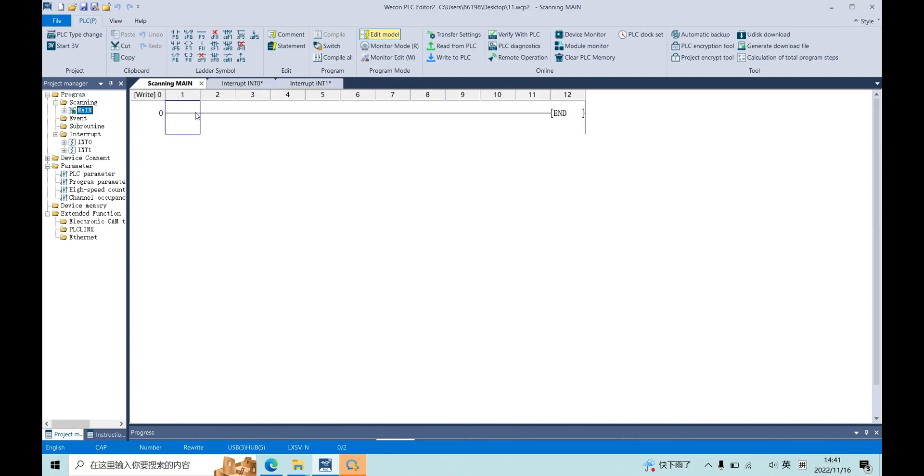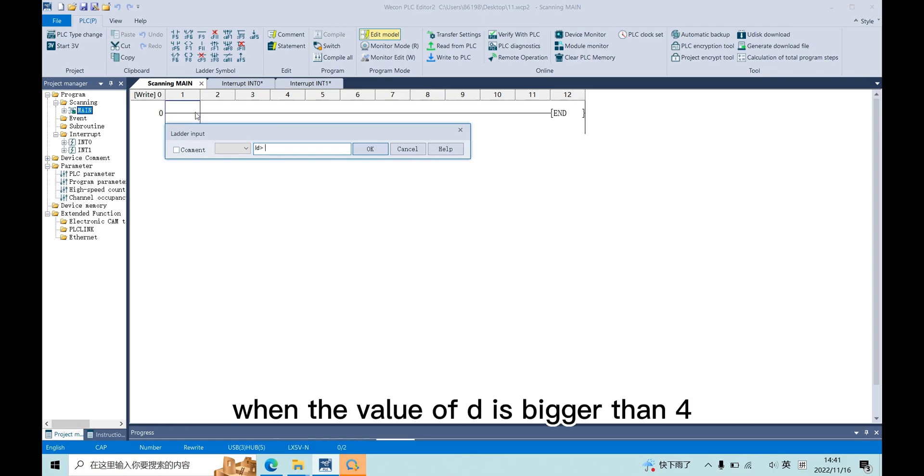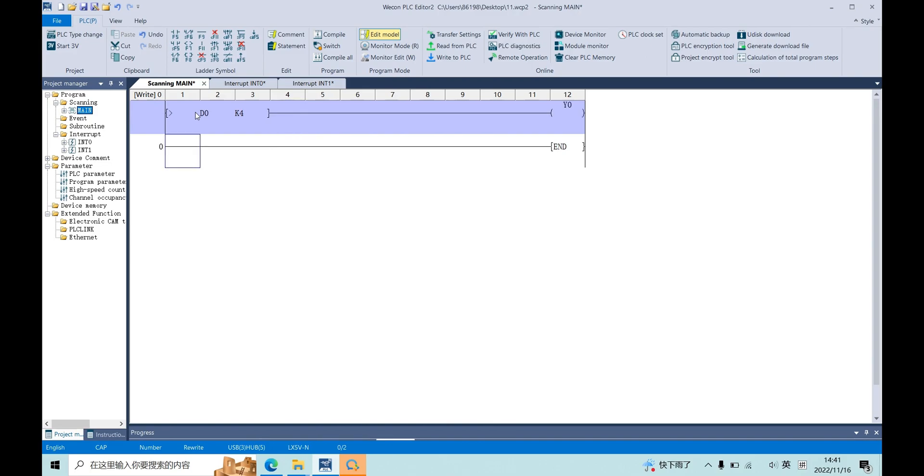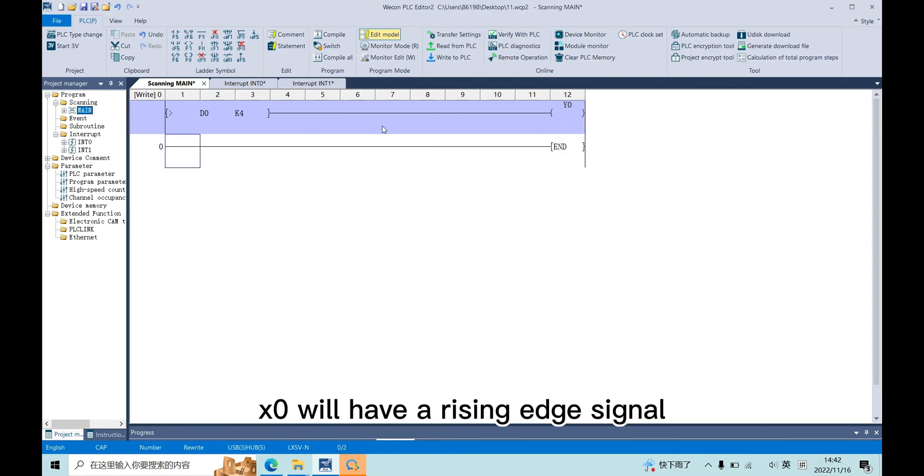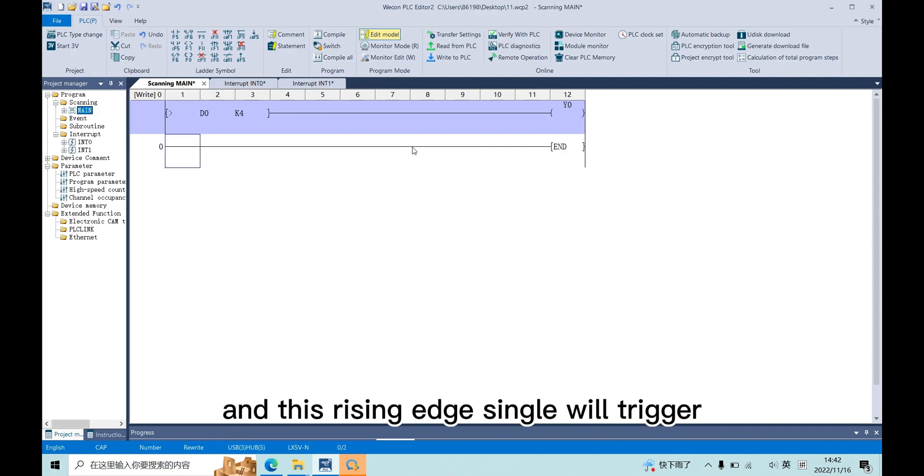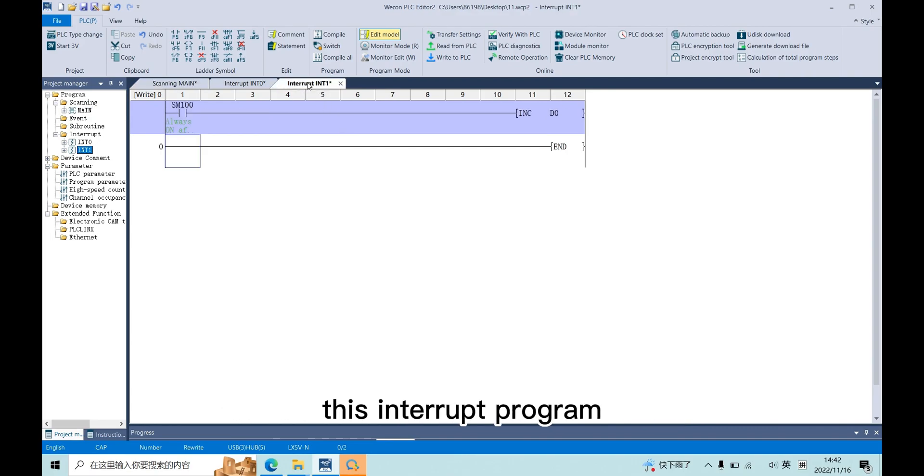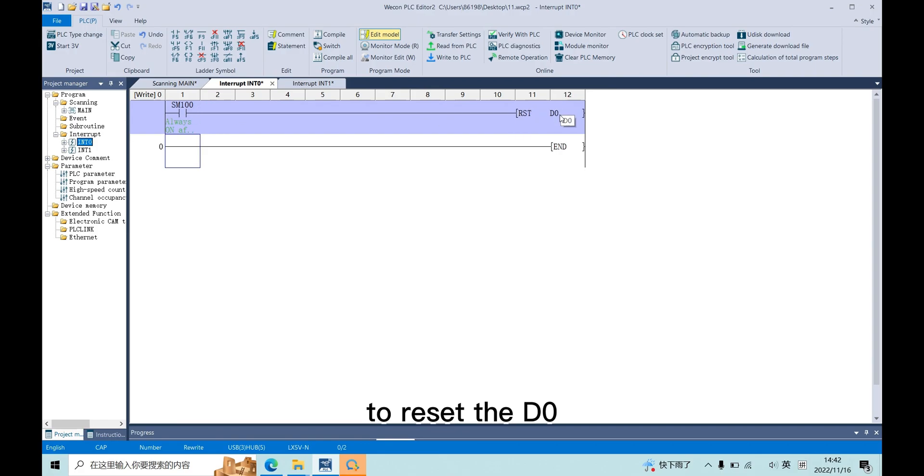In the main program, when the value of D0 is bigger than 4, output Y0. In PLC, I connect Y0 to X0, so when Y0 is output, X0 will have a rising edge signal. And this rising edge signal will trigger this interrupt program to reset the D0.